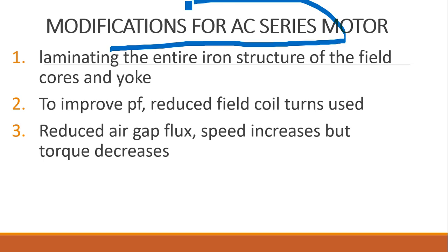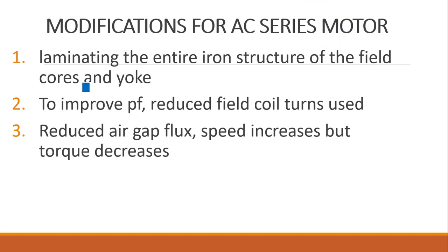What are the items to be done? There should not be eddy current loss, so we are laminating the entire structure. Maybe the stator and rotor, everywhere we will be laminating the structure. Okay, and the second problem was with the power factor because of the higher inductive reactance.